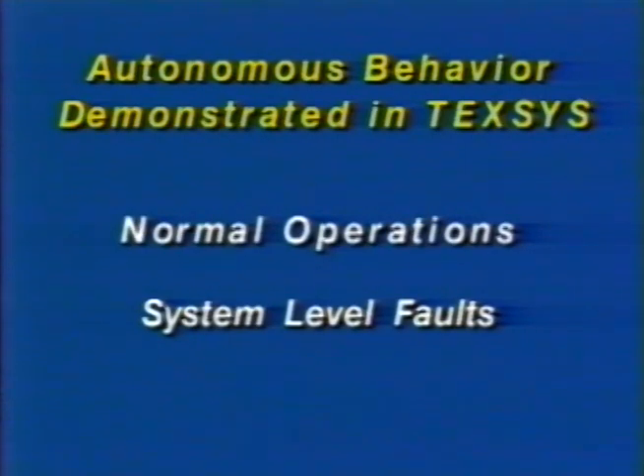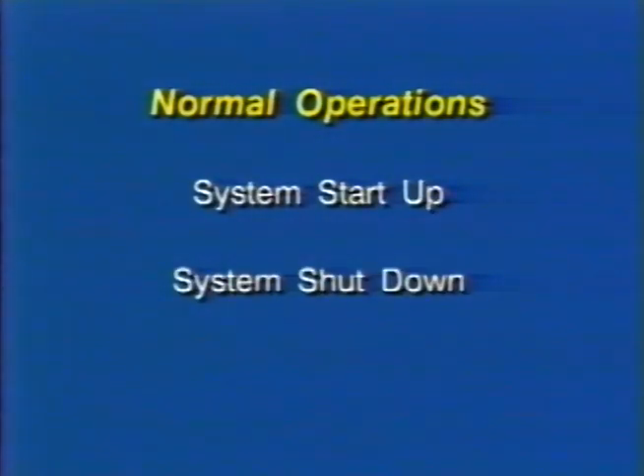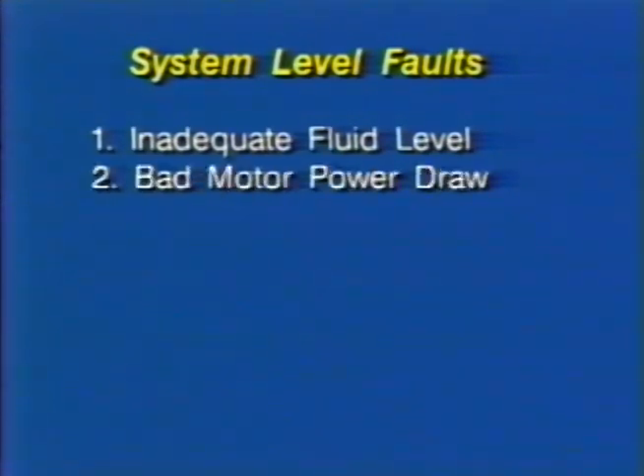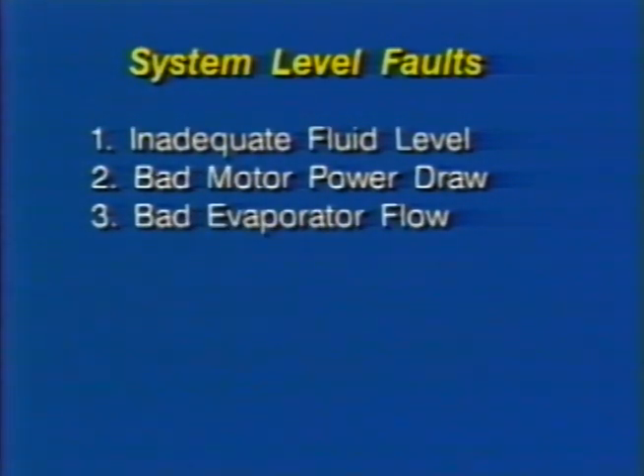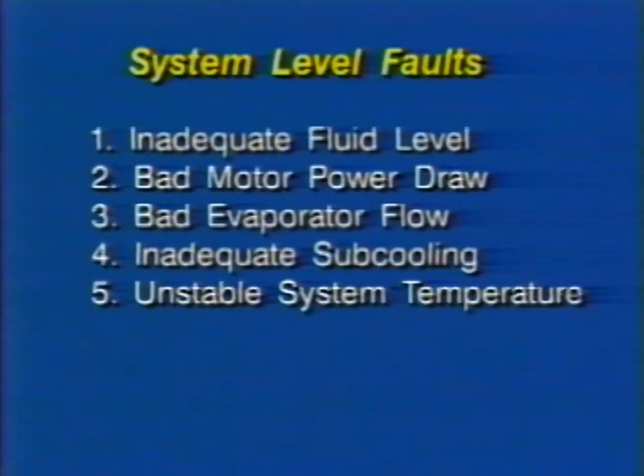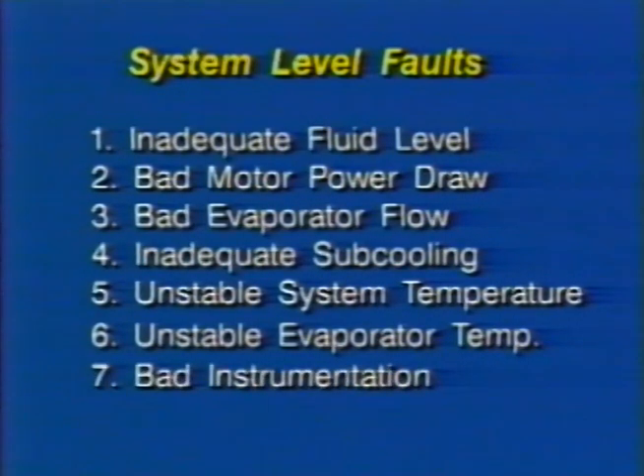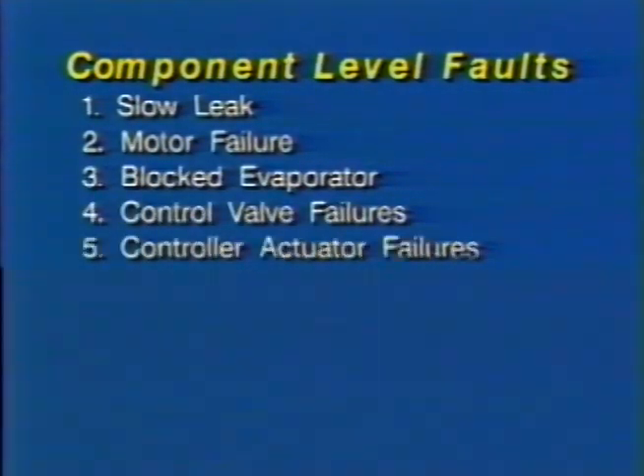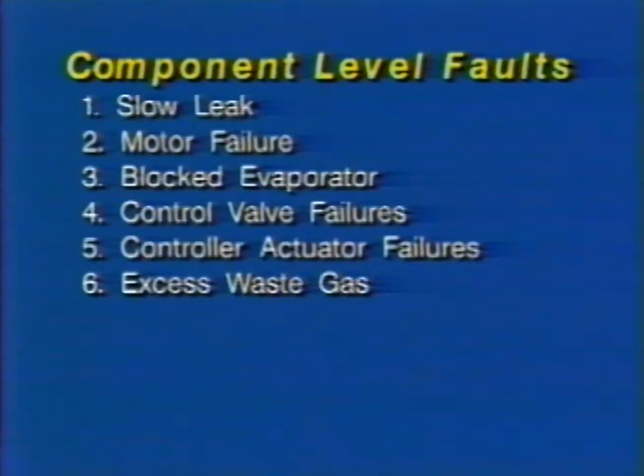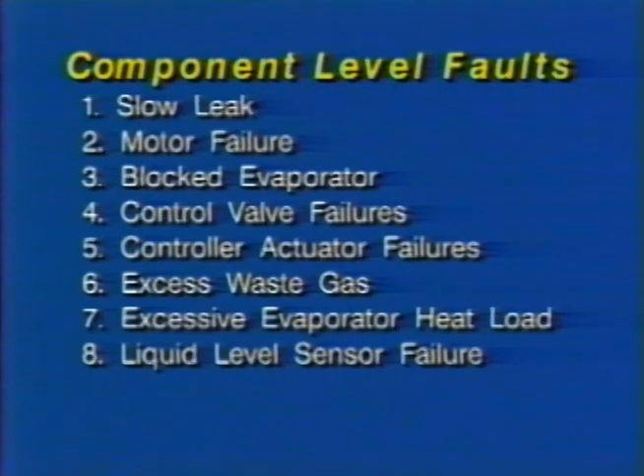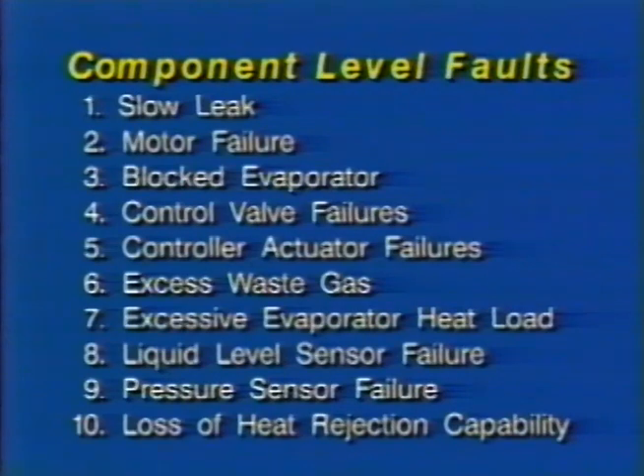There are three groups of behavior in TEXSYS: normal operations, system-level fault processing, and component-level fault processing. The normal operations include procedures for system startup, system shutdown, and temperature set point change. The system-level faults include inadequate fluid level, bad motor power draw, bad evaporator flow, inadequate subcooling, unstable system temperature, unstable evaporator temperature, erroneous instrumentation. Component-level faults include slow leak, motor failure, blocked evaporator, control valve failures, controller actuator failures, excess waste gas, excessive evaporator heat load, liquid level sensor failure, pressure sensor failures, loss of heat rejection capability.